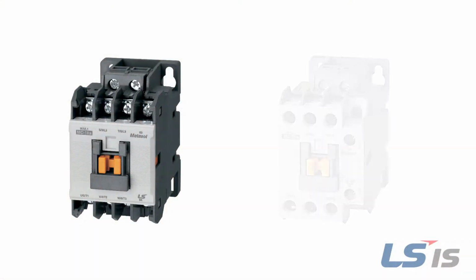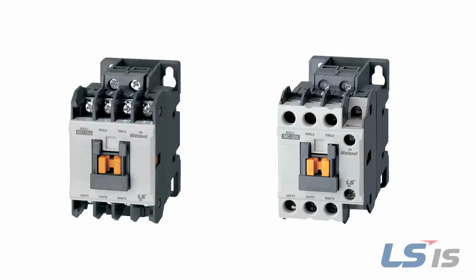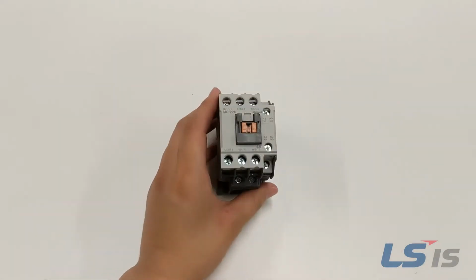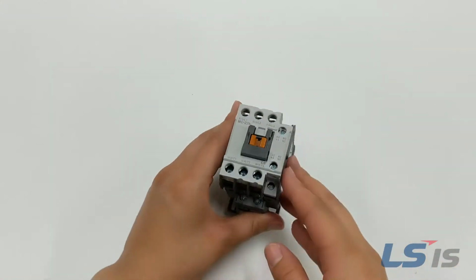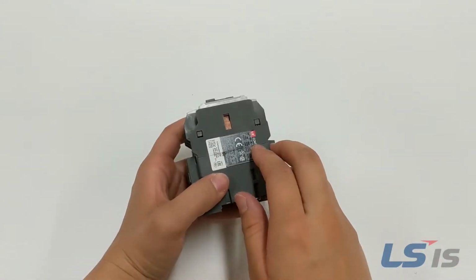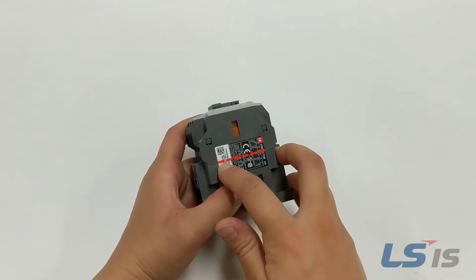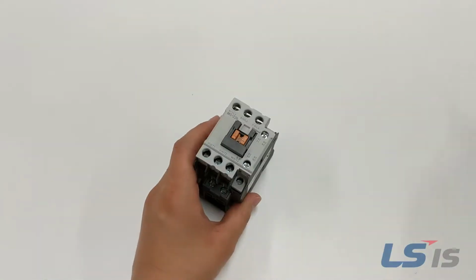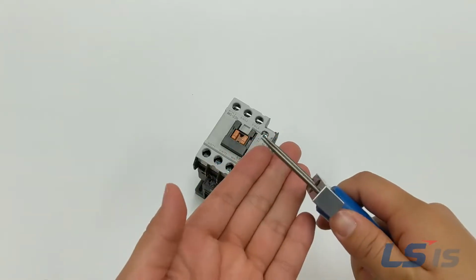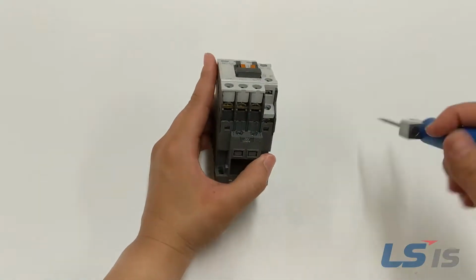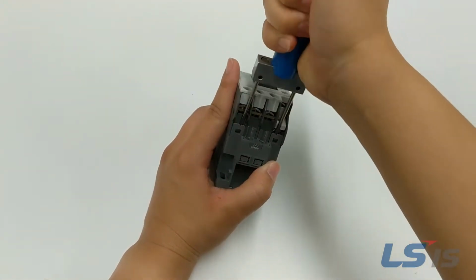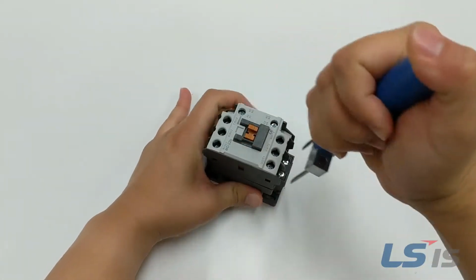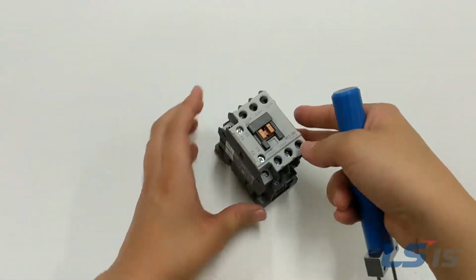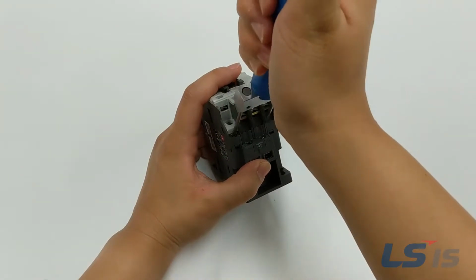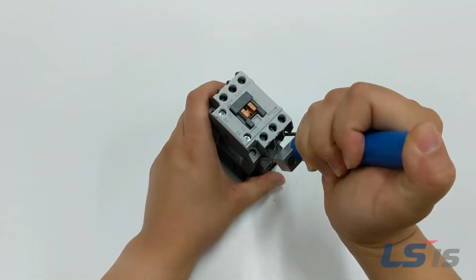For the MC 18M frame to 22M frame, as well as MR 4 to 8 frame contactors, remove the contactor from the box and place on a flat surface. Next, cut the nameplate label along the seam. Using your LSIS contactor tool or a flathead screwdriver, insert the blades into the outer plastic tabs and pull toward the body of the contactor in order to separate the tabs from the top. Repeat on the other side to fully separate the bottom half from the top half.